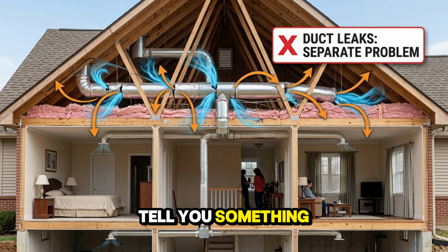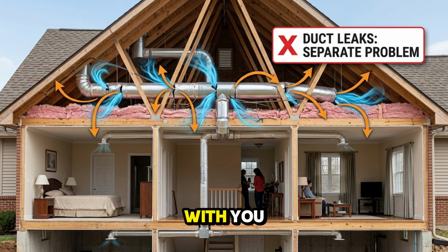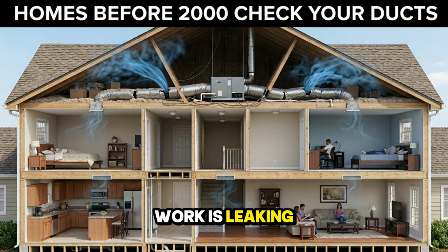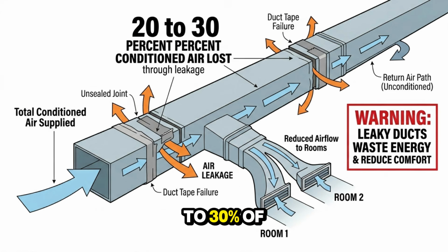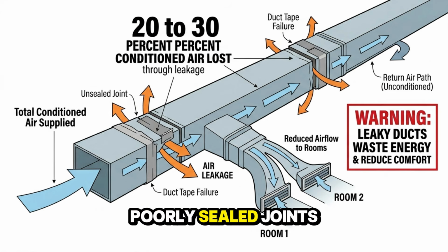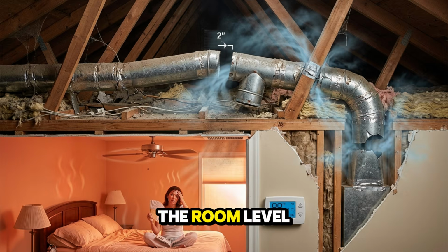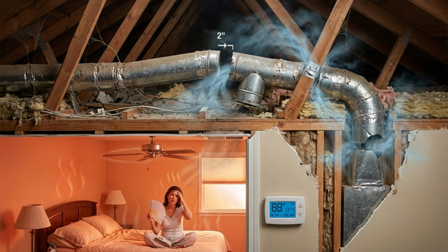Now I want to tell you something honest, the way I always want to with you. This trick does not fix duct leaks. If your ductwork is leaking, and in most homes built before 2000, ducts lose 20 to 30% of conditioned air through gaps and poorly sealed joints, a fan at the room level is working around a bigger problem. Duct sealing is a separate project, and it is worth doing.